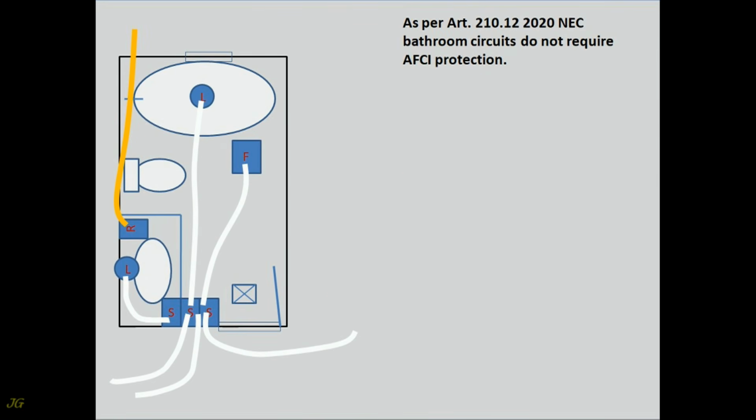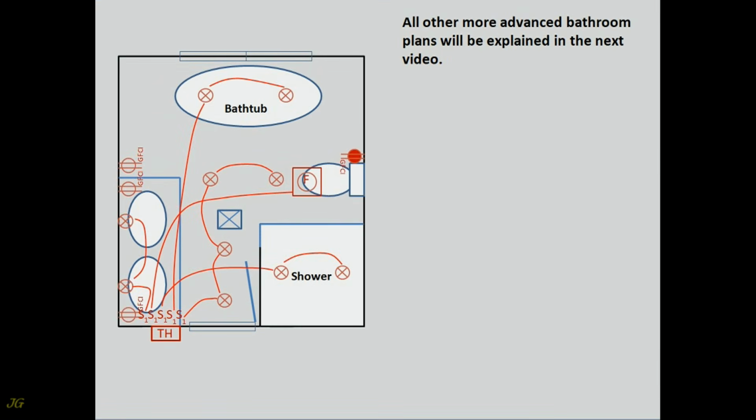As per Article 210.12 of the 2020 NEC, bathroom circuits do not require AFCI protection. All other more advanced bathroom plans will be explained in the next video.